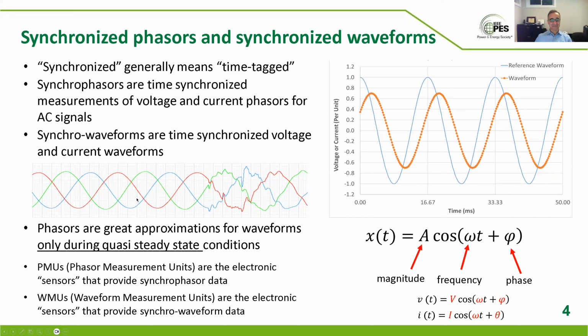In quasi-steady state, phasors are very good. There's a lot of great applications. In the last 10 years, they have picked up quite a bit in terms of application. The concept is much older than that, but the applications are growing. And waveforms are, again, 2 orders of magnitude more data. Local waveform use has been used forever. All your relays, meters, power quality recorders, these all have been capturing waveforms for a long, long time. Now we are trying to say, what if we could time tag them to microsecond and use multiple measurements at different places that we can compare with each other? So we call them synchronized waveforms.